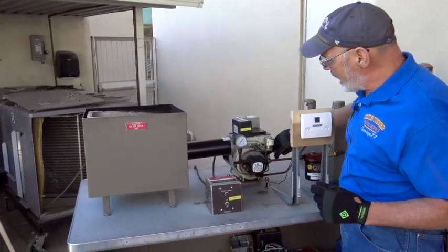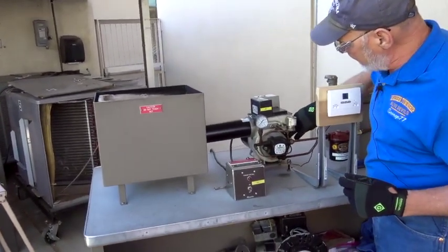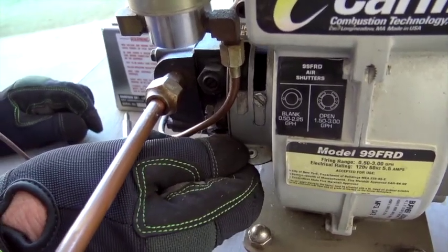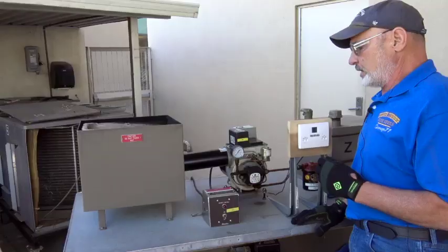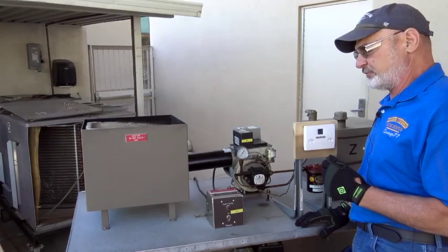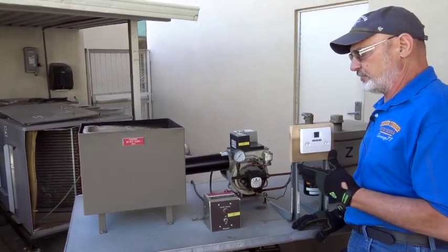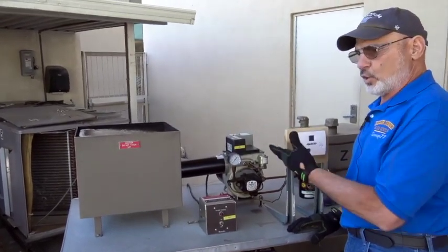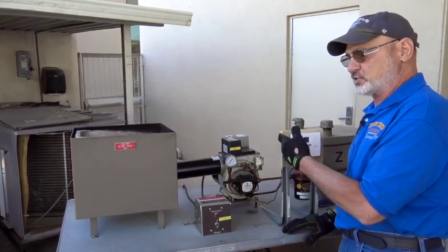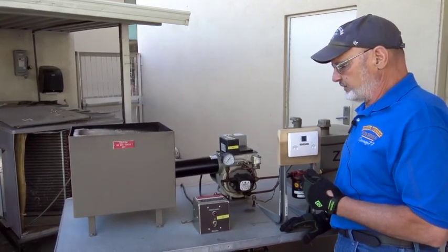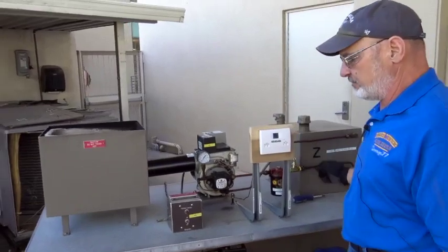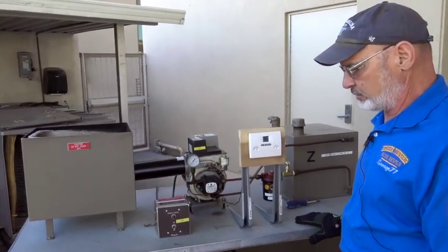We're going to show you how you can adjust this band on here to get more combustion air and less. Usually you'll have to have a very expensive combustion analyzer to do this for you, if you're working on any type of combustion, especially oil. This is a number 2 oil, as I stated before, that's used on this particular operation.